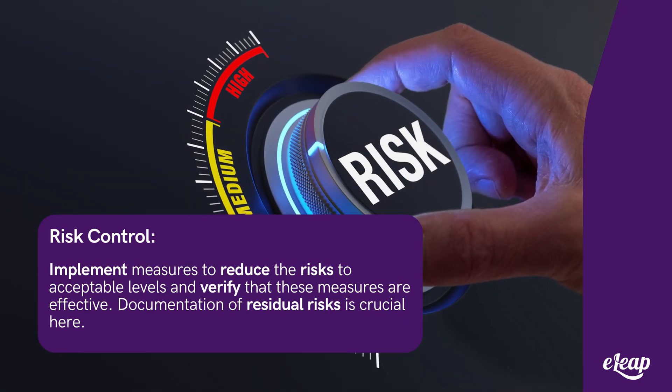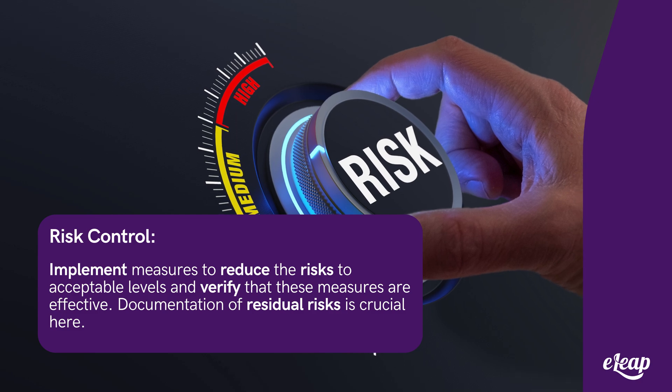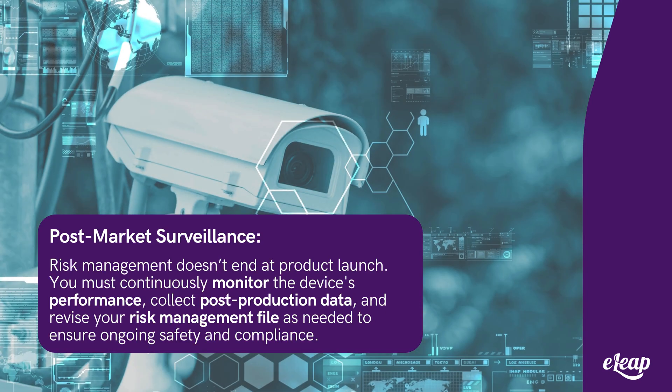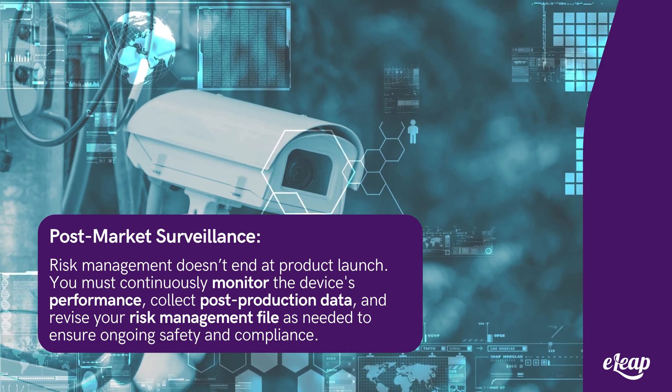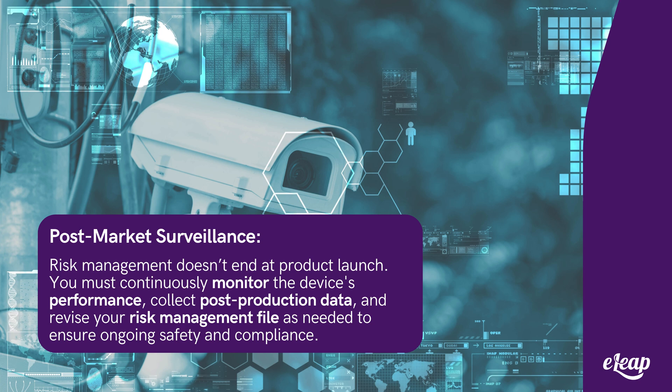Risk control: implement measures to reduce the risk to acceptable levels and verify that these measures are effective. Documentation of residual risks is crucial here. Post-market surveillance: risk management doesn't end at product launch. You must continuously monitor the device's performance, collect post-production data, and revise your risk management file as needed to ensure ongoing safety and compliance.